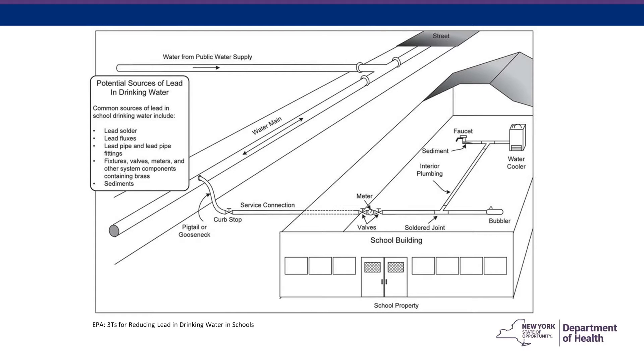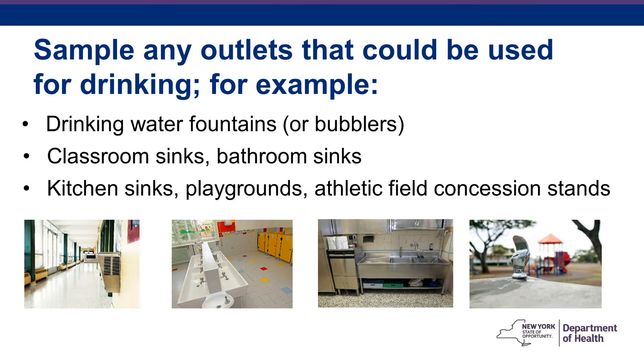Before testing for and correcting lead problems, evaluate the school building's plumbing system and assess the factors that may contribute to lead contamination. An evaluation should identify all outlets that are used or could potentially be used for drinking and/or cooking purposes. All identified outlets must be sampled for lead, including drinking water fountains or bubblers, classroom sinks, bathroom sinks, kitchen sinks, and athletic field concession stands. Based on this information, the school can develop a sampling plan, including assigning unique identification numbers to each outlet to be sampled.